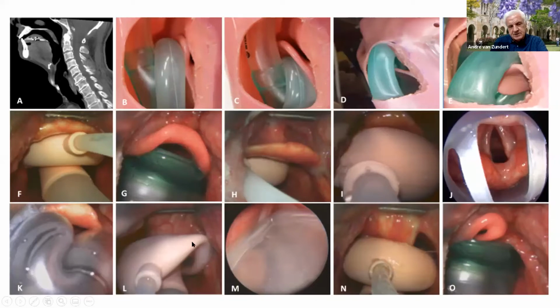Here the tip is folded backwards. It does not sit in the esophagus. There's no clear second seal, and that can result in aspiration of stomach content. And here the distal cuff of the device sits between and across the vocal cords, creating a massive leak, and again, that can result in aspiration. This is the epiglottic downfolding that occurs quite often, or even sideways. So the epiglottis is now folded double in here.